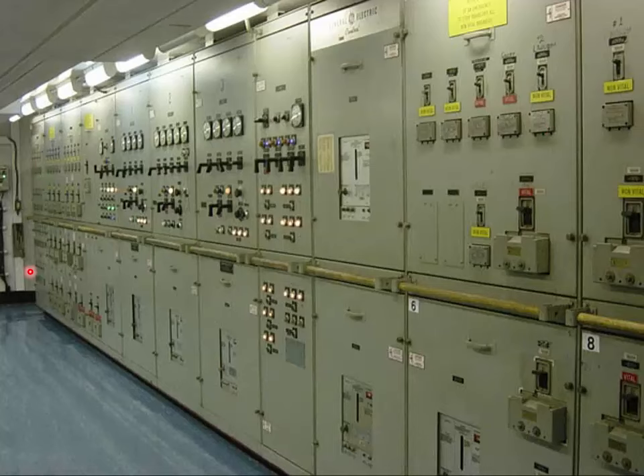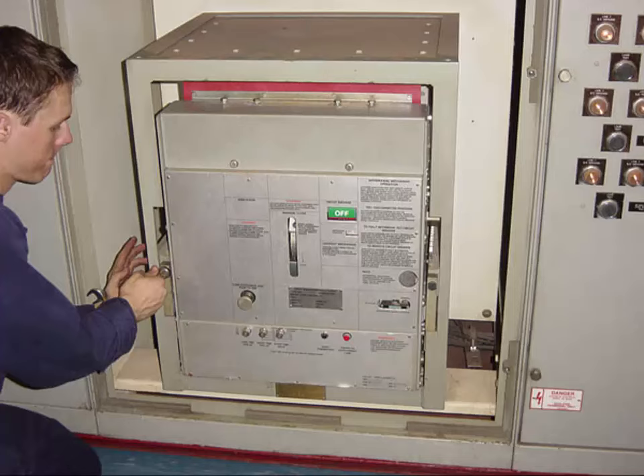Down on this end, you actually have the 115 volt lighting distribution panel on this extreme left-hand side of this switchboard. The rest of the switchboard is all going to be 440 volt distribution. This is a picture of one of our motorized circuit breakers. We don't have time to get into this too much, but again, these are designed for large overloads. They can handle a lot of current, and it has two settings.